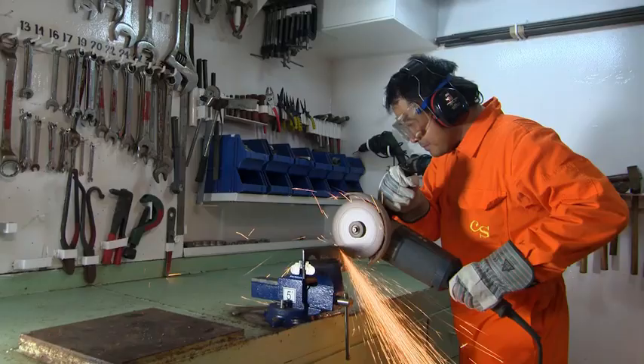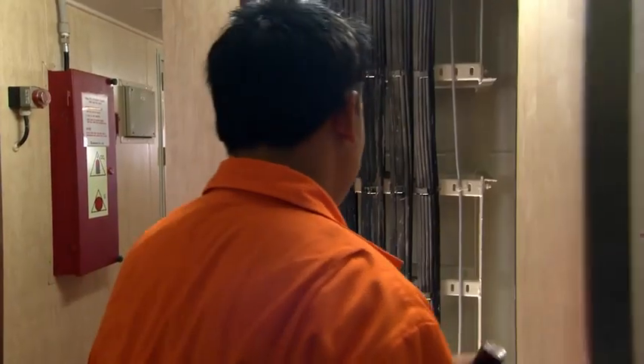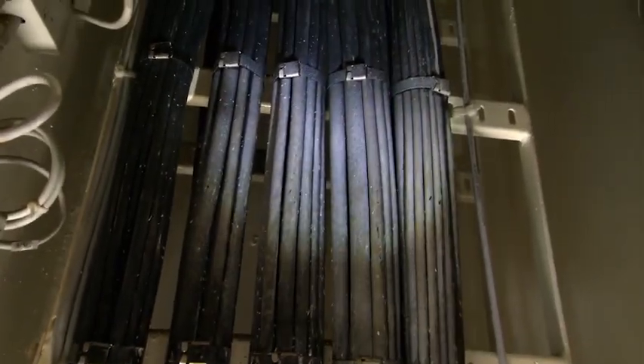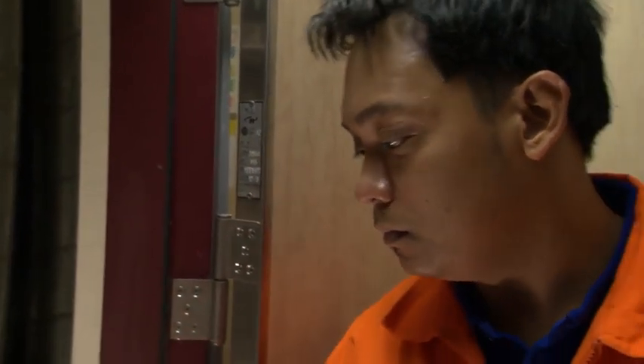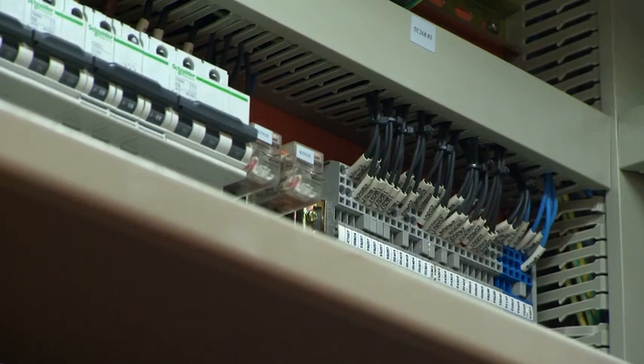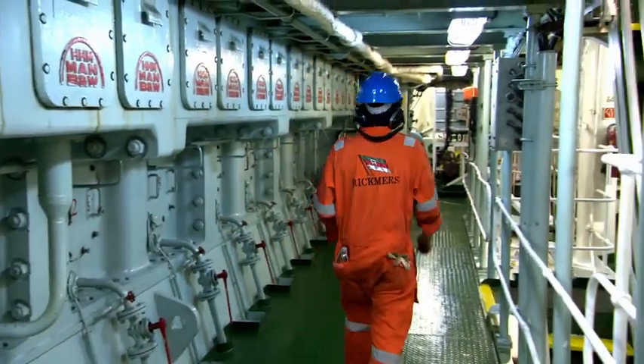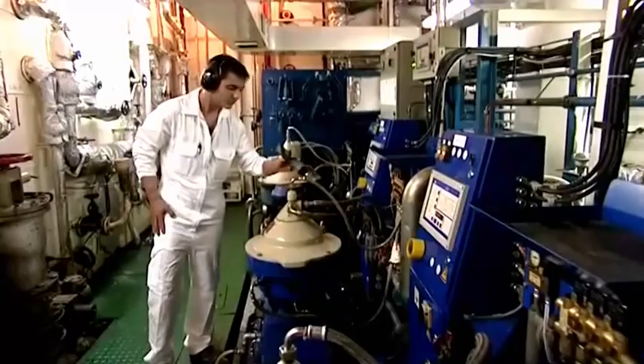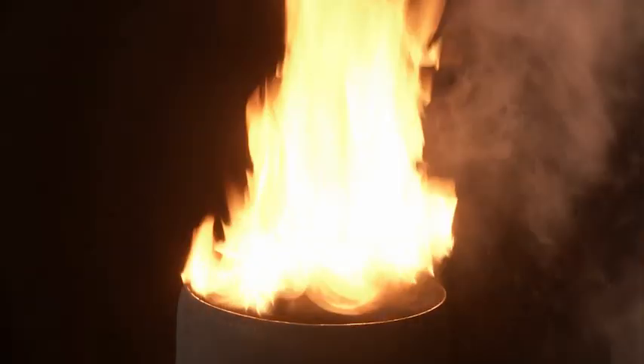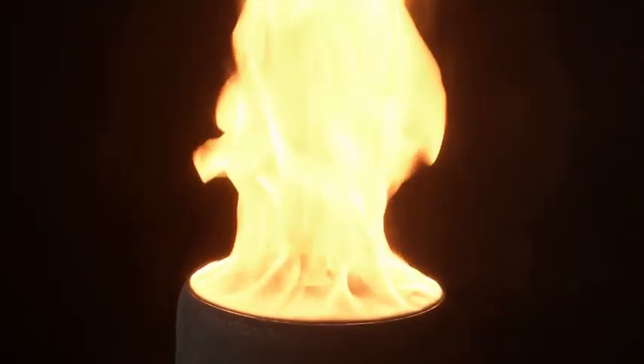These include sparks from angle grinders and welding equipment, high-voltage electric cables. Be particularly careful of the bus bar and any red-coloured cables. The hot, dry atmosphere in a machinery space, which is ideal for the build-up of static charges. And engines, pumps and other machinery which generate heat. Remember, hot surfaces can also vaporize flammable liquids, changing a safe product into an unstable combustible gas.